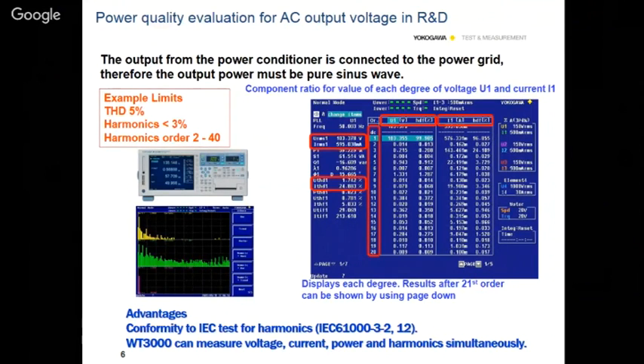The WT3000 can measure voltage, current, power and harmonics simultaneously, as per the IEC standards. There is one more option. The limits are that THD should be less than 5%, harmonic should be less than 3%, and harmonic order should be 2 to 40, with no harmonics beyond 40. This is the limit of one of the IEC standards.